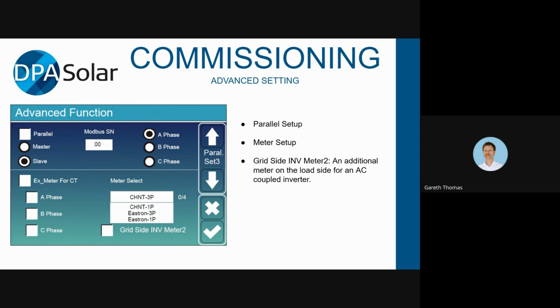If you're wanting to do three-phase, there's no option to have three single-phase inverters set up in a three-phase arrangement like you would with Selectronic. You would just get a three-phase model. If you need a larger system than any of the three-phase models offer, you would use multiple three-phase inverters in parallel. Or if you have a single-phase setup and you need something bigger than any of the single-phase models, you're going to put them in parallel. So you're going to tick this parallel button here. You're going to select one of them as the master, and the other ones are going to be the slaves.